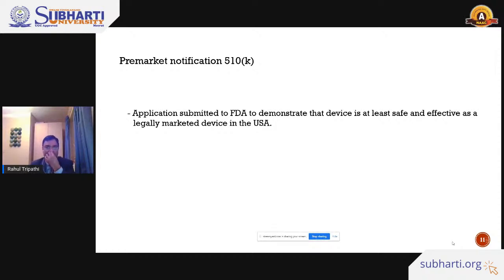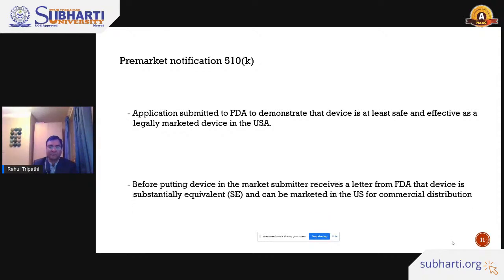Pre-market notification. An application needs to be submitted to the FDA, as I mentioned earlier, to demonstrate that devices are at least as safe and effective as a legally marketed device in the US basically. That's why pre-market notification is also an alternative name of the 510k form. Before putting those devices on the market, a submitter receives a letter from the FDA stating the device is substantially equivalent and can be marketed for US commercial distribution.